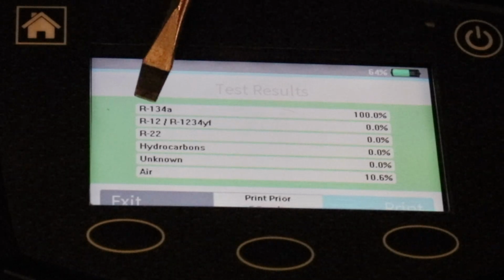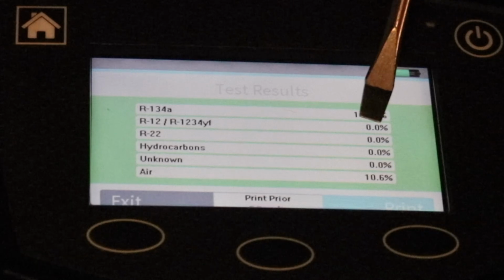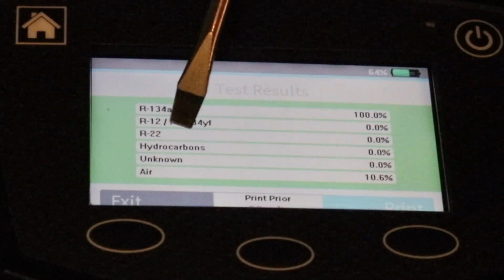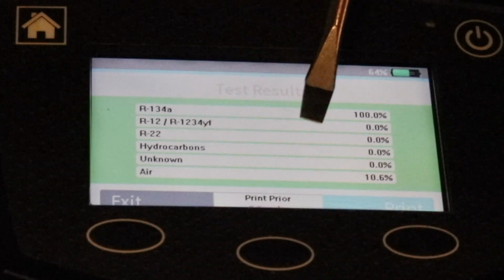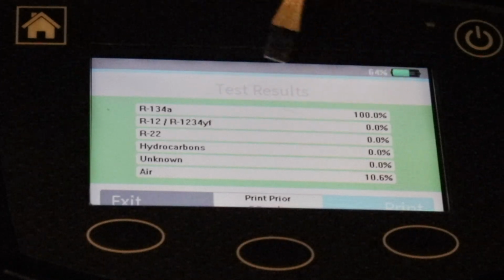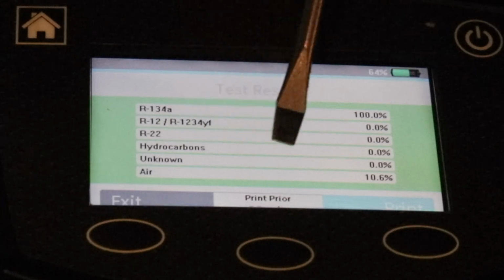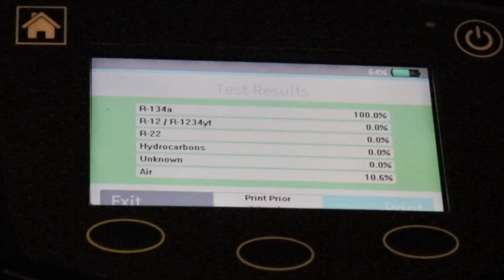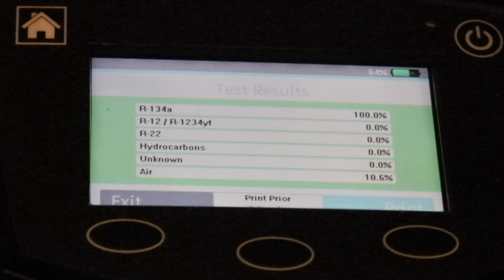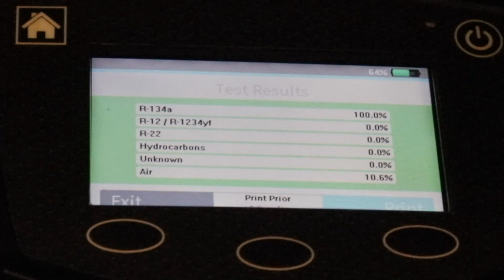Indeed, if we go to the next line where we're displaying other substances, R12, 1234YF, R22, you'll see that they all read 0%. Hydrocarbons or flammable refrigerant, 0%. Unknown substances, 0%. But here's the one I'm interested in, air content, 10.6. That's extremely high, and that is a cause for concern. Air content carries moisture, it displaces refrigerant, causes excessive head pressures, and gives you similar symptoms to a system overcharge.